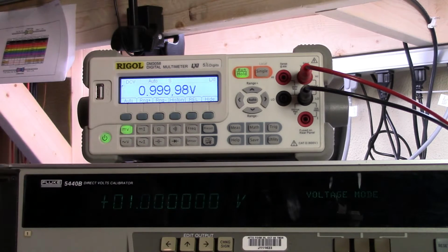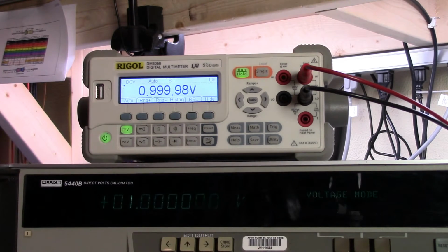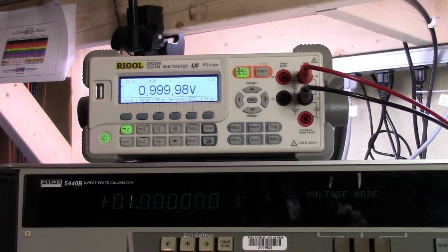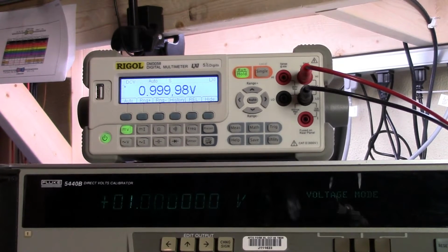I think there might be a problem because I think the unit's supposed to have a fan in it. I don't remember. We'll have to take the cover off and have a look and see if there's a fan and why it isn't running. And then we can let it warm up. Why don't I take this out and swap in my 3458A and get a real good look at what the voltages are. Be right back.